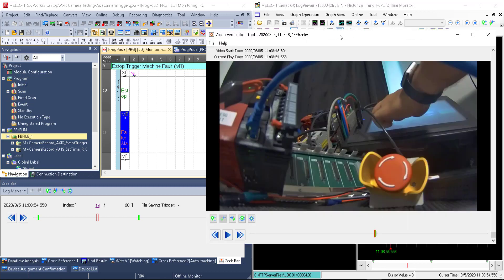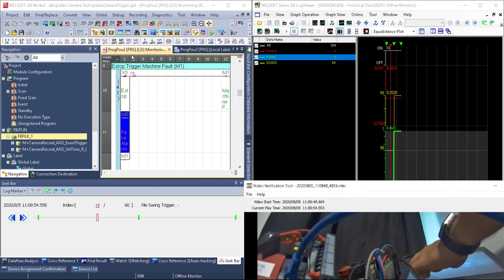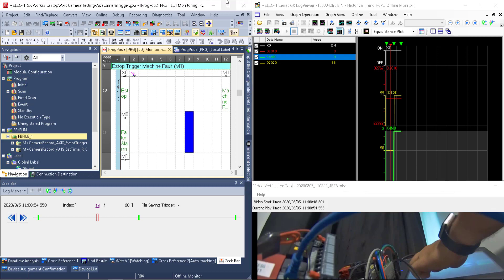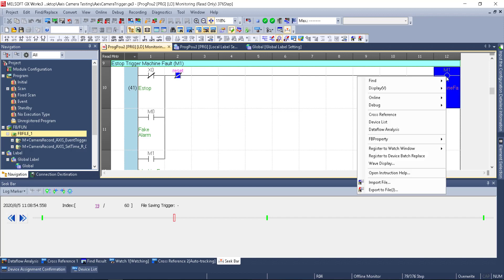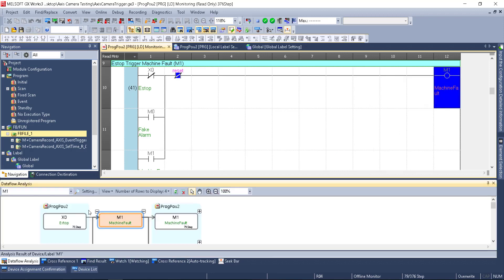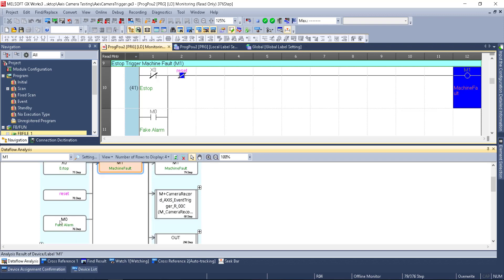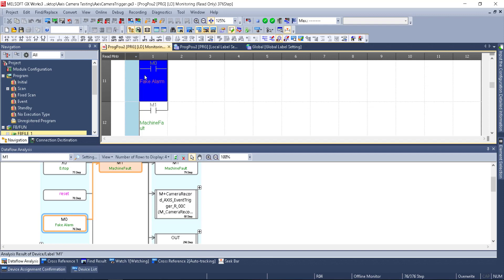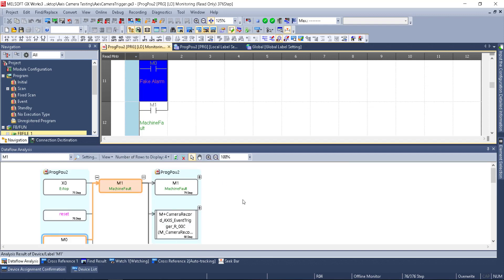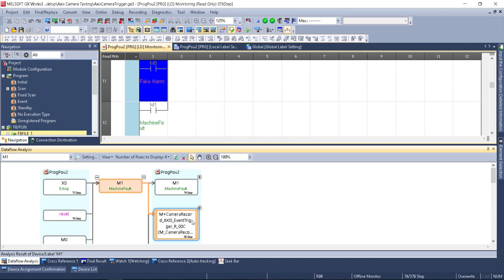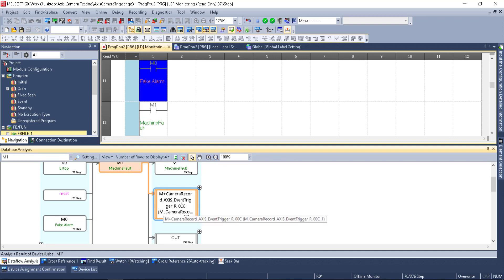This is pretty powerful stuff — syncing the video file, actual logging information, offline ladder monitor, and GX Log Viewer, all linked with log marker data. And the last thing to show: if I right-click I can say data flow analysis, which shows what triggers M1 — either X0 the E-stop or M0 the fake alarm — and takes me directly to that location in the ladder. That's how data flow analysis comes into play when we're in offline monitor mode.